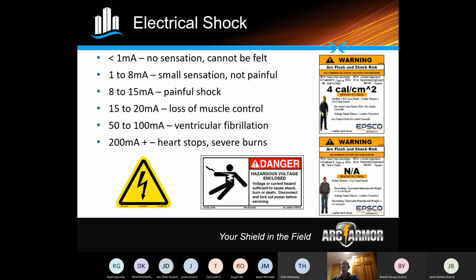On the right-hand side here are some warning labels that would result from a short circuit analysis and also an arc flash analysis. It used to be PPE 1, 2, 3, or 0, 1, 2, 3, with 0 basically meaning you could go in with just gloves, proper clothing, a cotton shirt, those types of things. They've refined that a little bit, so it's based on the energy that's stored and available that could cause issues.